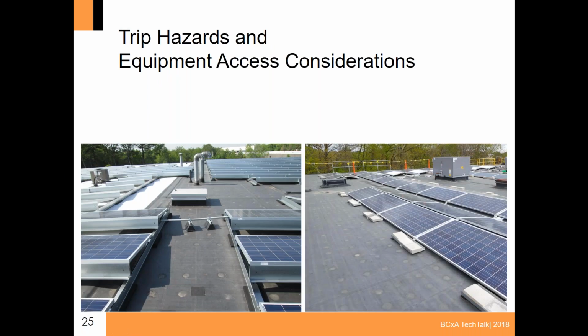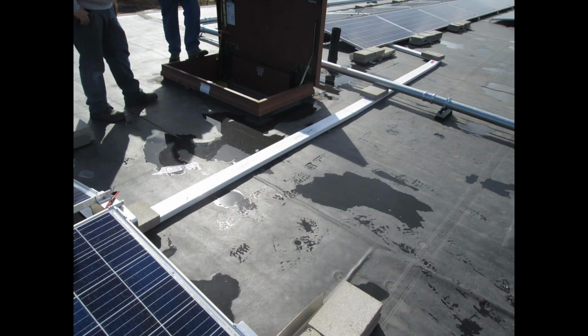One of the things the designs may or may not show would be these trip hazards that we encounter after the fact. So it's inevitable that the conductors will need to cross these pathways at some point, but we really try to ensure that these hazards are mitigated in the initial system design. On the right, you can see the modules are completely obstructing access to the rooftop HVAC equipment. And again, just another design consideration that could have been avoided as well. In this case, we see a low-profile cable tray right over here, directly exposed to physical damage. It's also a trip hazard for workers accessing the roof. So again, during construction or ahead of construction, we should lay out how do we get conductors from this side to this side, and is this the best method?